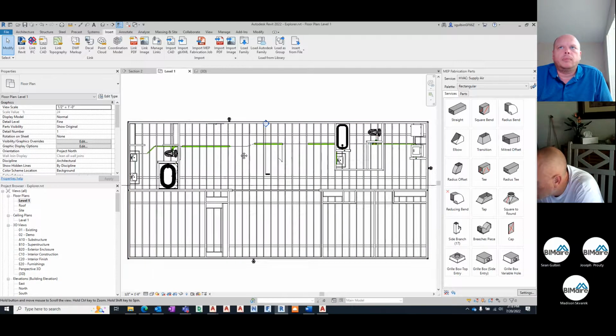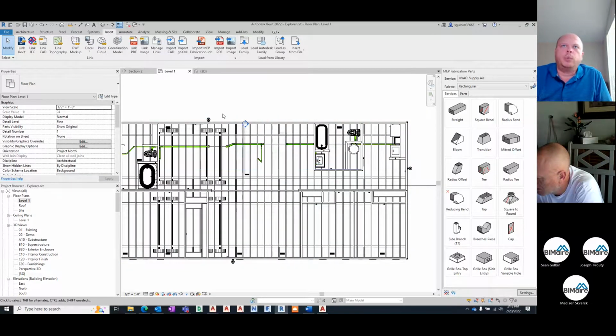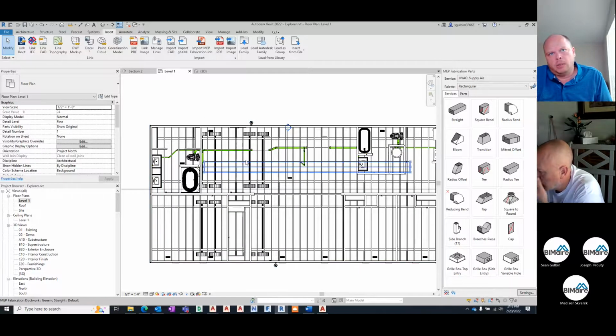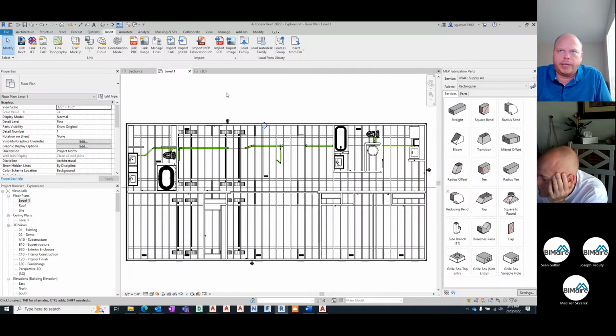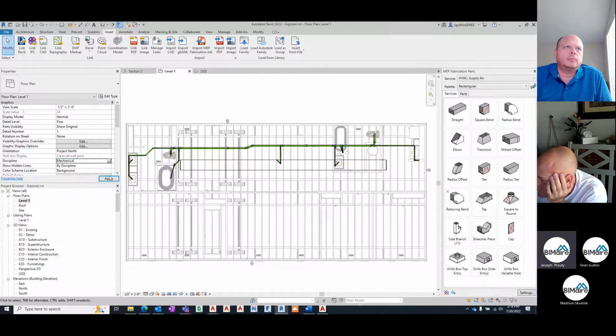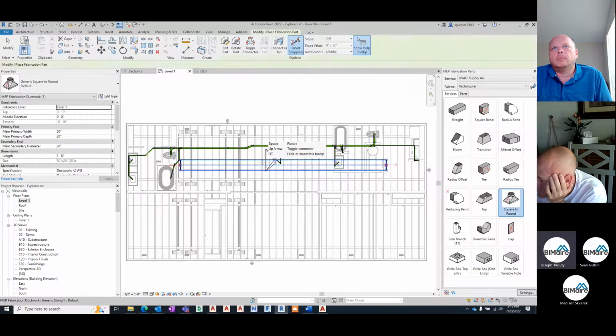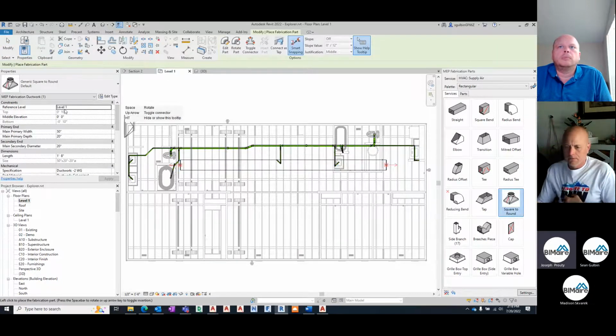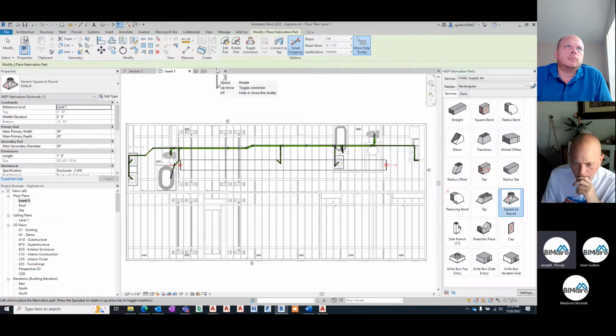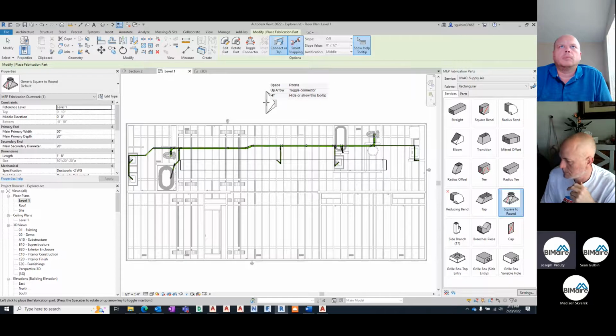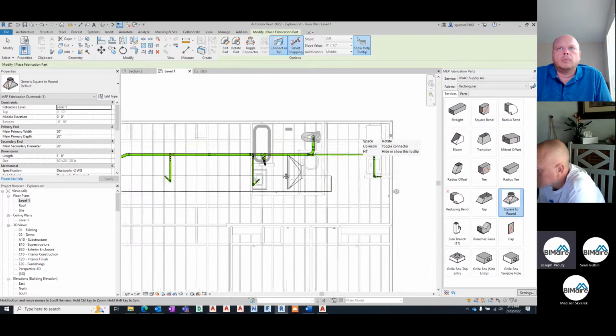All right. So Joe, you've got to instruct here. What should we do here versus the CAD side? I think the Flex Duct is probably the only thing we should do on the CAD side. So go to your change. First of all, change your discipline here so that way you can see everything for the mechanical. Yep. Now you're in the duct, and now you just want to put in this square-to-round tap. Yep. And then check on the ribbon, it says connect as tap. Click that button. Yep. Now you can just click your ductwork. So it should snap right to it.